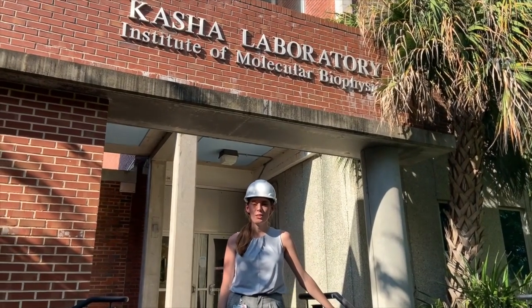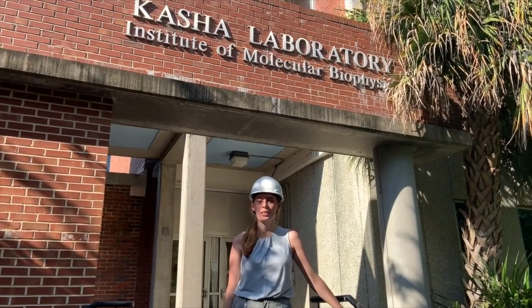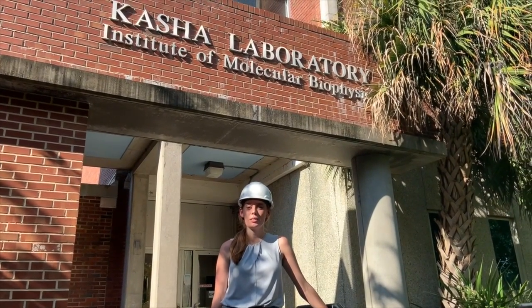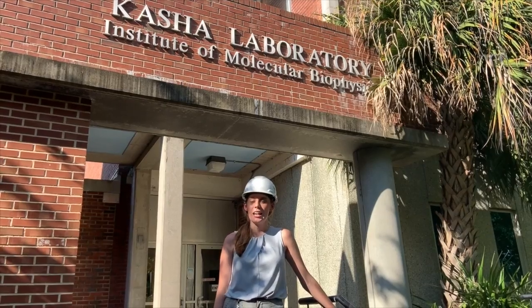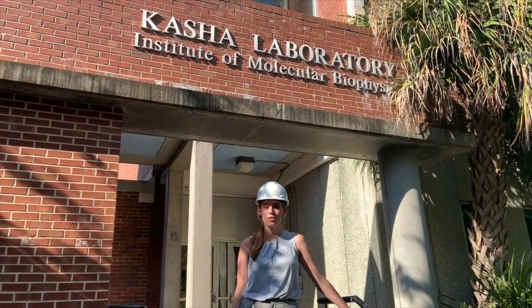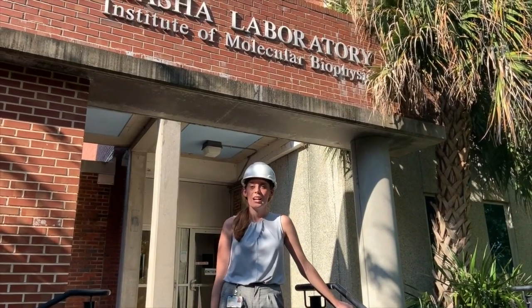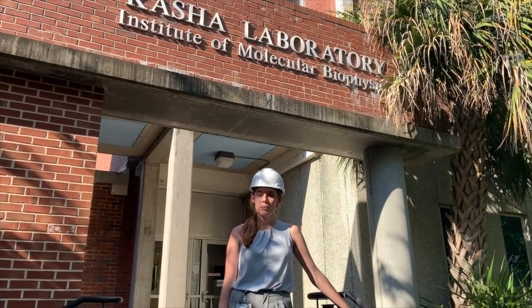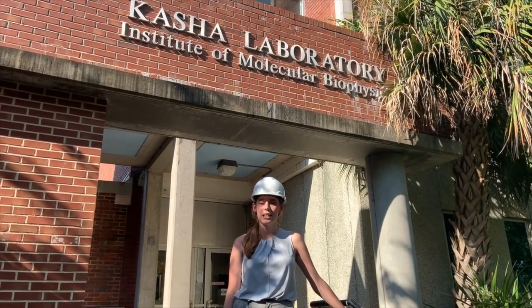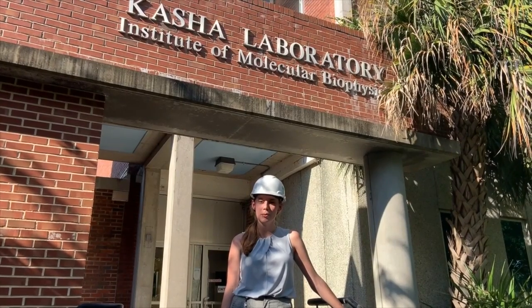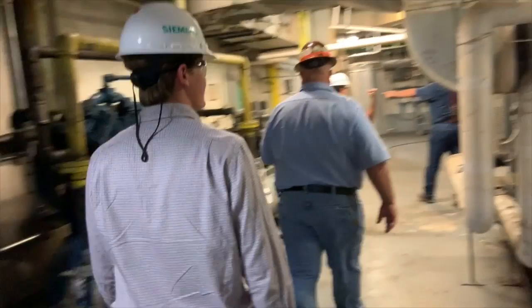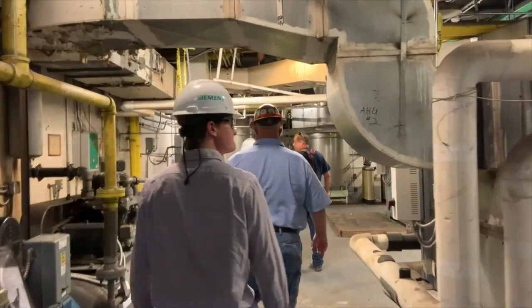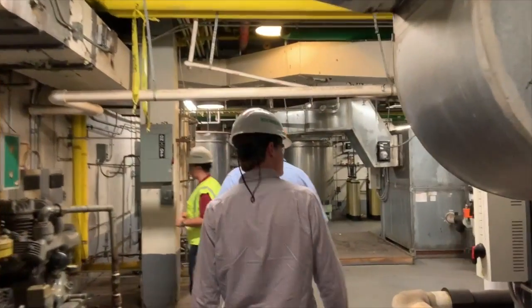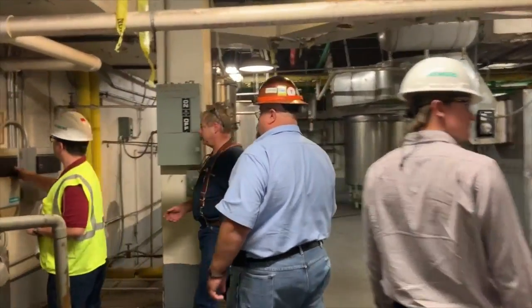I'm here at the FSU Kasha Laboratory at the Institute of Molecular Biophysics. This building was constructed in 1963 and renovated in 2002. It's five stories and mixed use with both offices and laboratories, so there are special ventilation requirements. Siemens has been tasked to commission this building, see how it's currently operating, and identify ways to improve building performance and energy efficiency. The building systems evaluated include the air handling units, exhaust fans, and variable speed chilled water and hot water pumps.